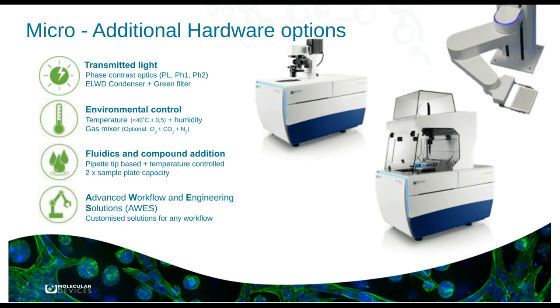Looking more broadly, there are additional hardware options on the ImageXpress Micro Confocal. You can have transmitted light options for phase contrast imaging. There are live cell controls with CO2, temperature, and humidity to keep cells alive for longer periods. There is a fluidics module for compound addition and medium exchange, and advanced workflow and engineering solutions dealing with automation and customization of instruments — providing solutions that meet particular customer needs if the standard offering does not.